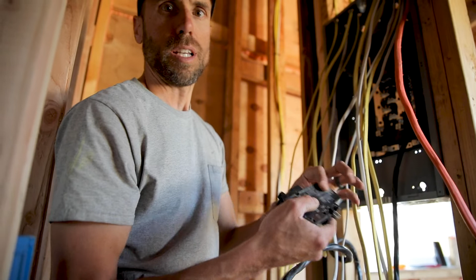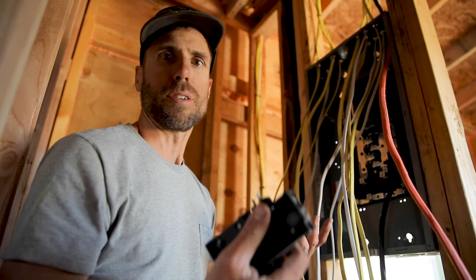So for arc fault circuit breakers, we're gonna connect the neutral wire and the hot wire here. So the hot wire will go in this hole here, and the neutral wire will connect here. And that neutral wire is connected to these here. So you can see how that's going to wrap around the neutral bar. So the neutral wire is kind of attached to the neutral bar, but it goes through here. And inside here is a little processor, a little tiny computer, and it senses if there's an arc somewhere. So it'll sense a little anomaly in the electrical current wave, and it'll trip the circuit breaker. It's called an arc fault circuit breaker. So you can see how when we put this on, that clip there is just gonna wrap around the neutral bar.